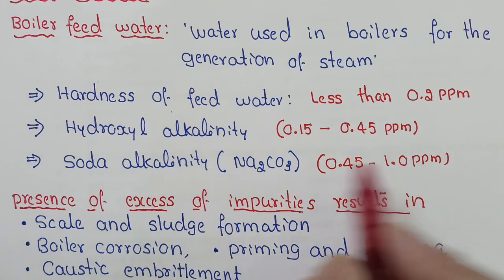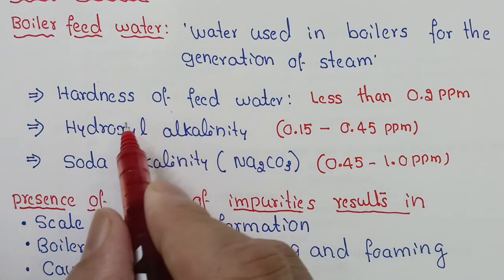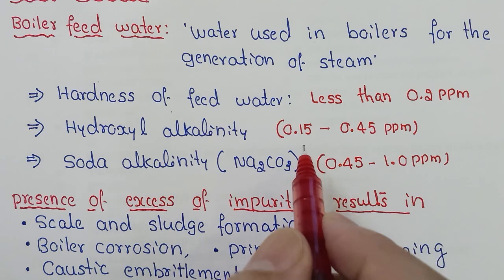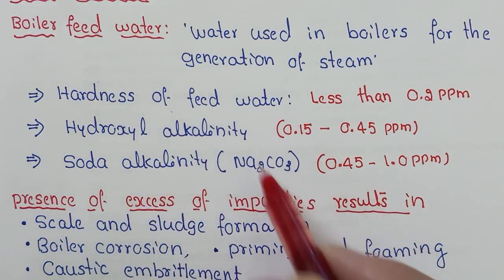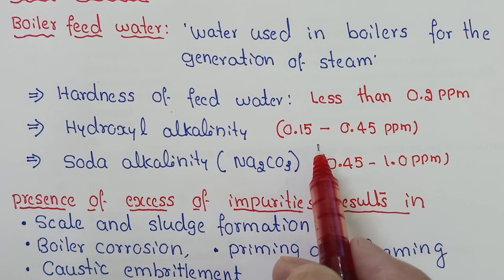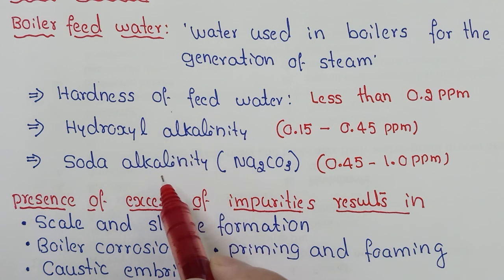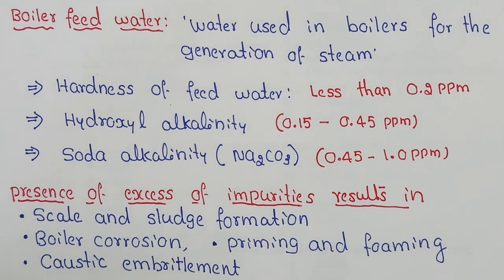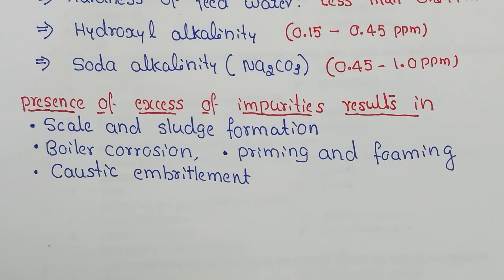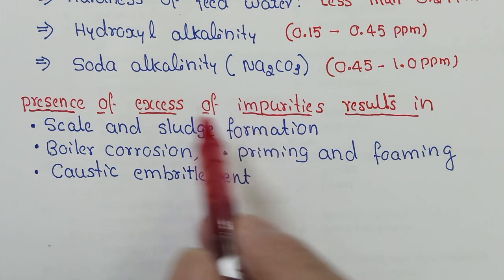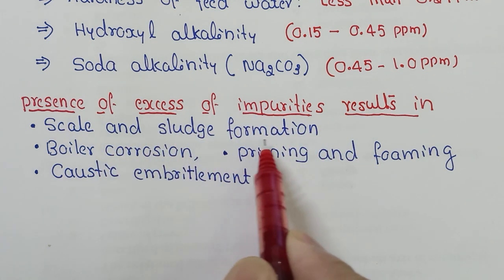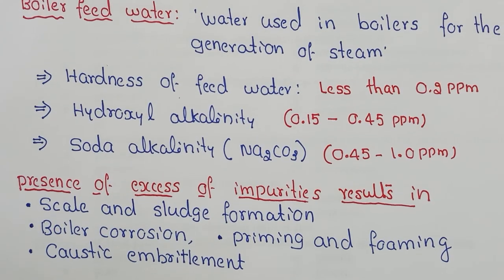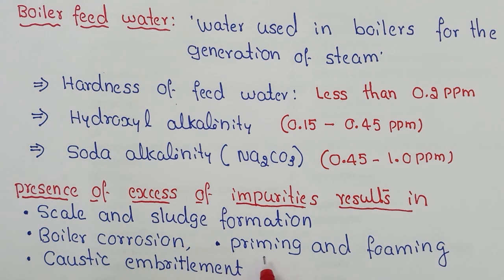If the soda alkalinity is between 0.45 to 1 ppm, hydroxyl alkalinity between 0.15 to 0.45 ppm, and hardness less than 0.2 ppm, these are within tolerable limits and the water can be fed into the boiler without causing much damage. However, if impurities in the form of hardness, hydroxyl, or soda alkalinity exceed these limits, it results in problems in the boiler — mainly scale and sludge formation, boiler corrosion, priming and foaming, and caustic embrittlement.